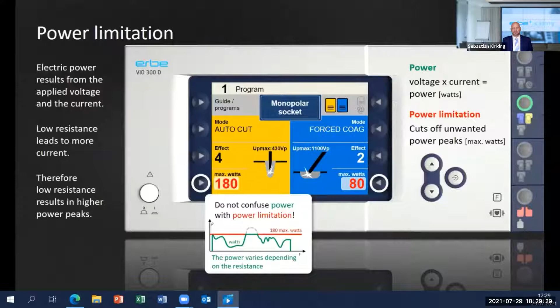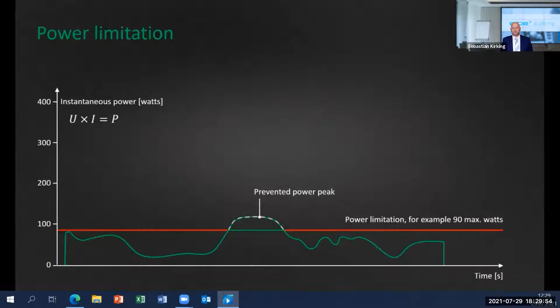Note that some units also have a power limitation to select from. This is sometimes misunderstood as power setting. As this graph shows, the electric power on such a voltage control device is a curve. With the power limitation, the red line, you can prevent excessive current, for instance, when the resistance is extremely low. Usually, these settings do not need to be adjusted all of the time unless it has been set too low and the tissue effect thereby becomes too weak.